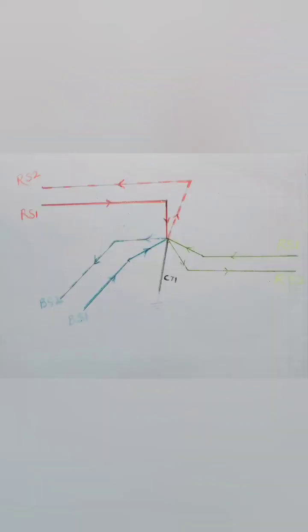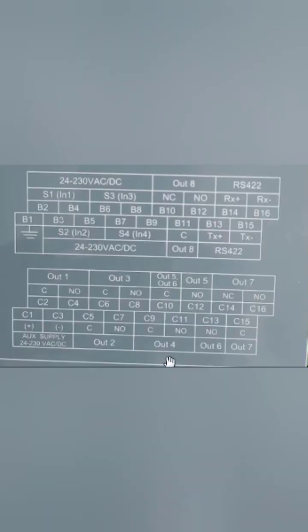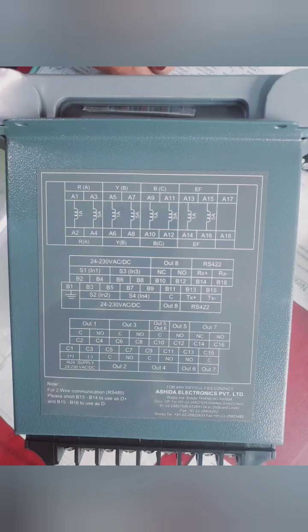During normal operation the current keeps flowing in secondary from S1 to S2 and very nominal unbalanced current flows through C71. During fault all NO become NC and NC's become NO's and the circuit breaker trips. Although connections are not difficult it should be done under supervision.